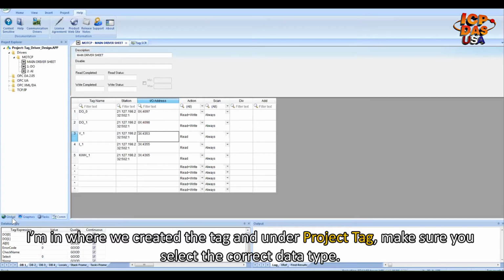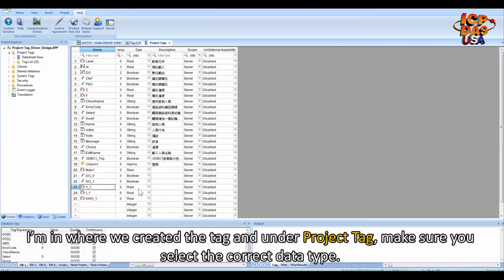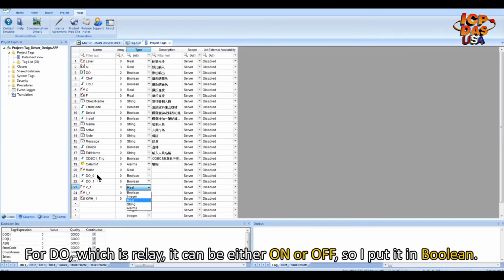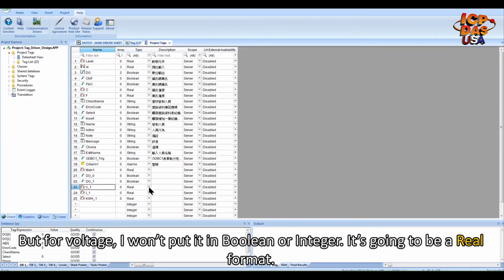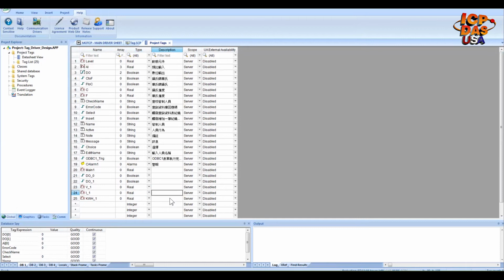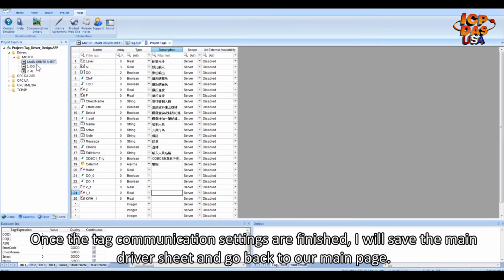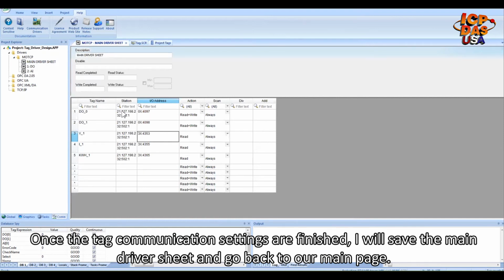So when we create a tag under project tag, make sure you select the correct data type. For DO, which is a relay, it can be either on or off, so I put it in Boolean. But for voltage, because it is a floating format, I won't put it in Boolean or integer. It is going to be the real format.